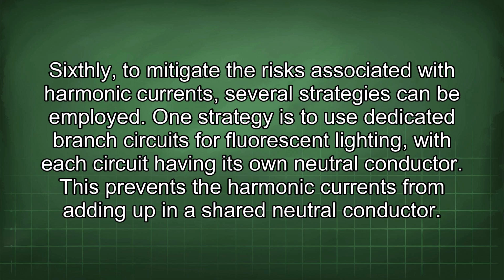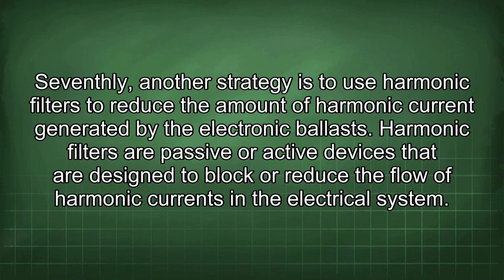One strategy is to use dedicated branch circuits for fluorescent lighting, with each circuit having its own neutral conductor. This prevents the harmonic currents from adding up in a shared neutral conductor. Seventhly, another strategy is to use harmonic filters to reduce the amount of harmonic current generated by the electronic ballast.